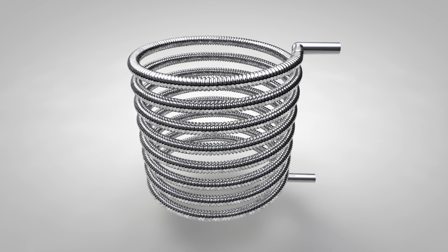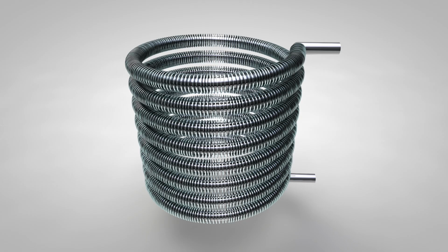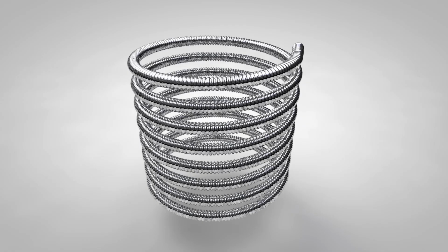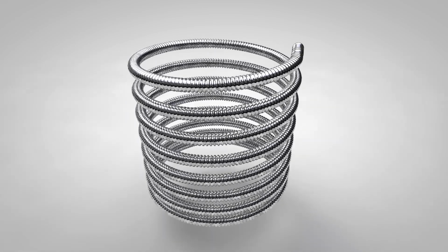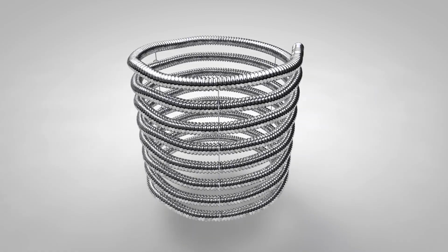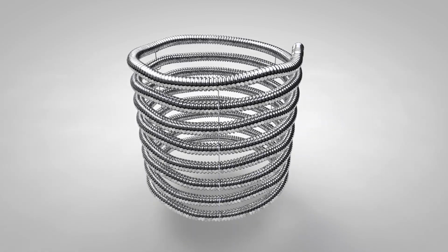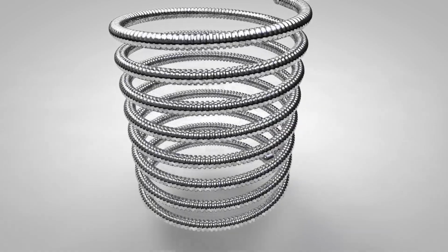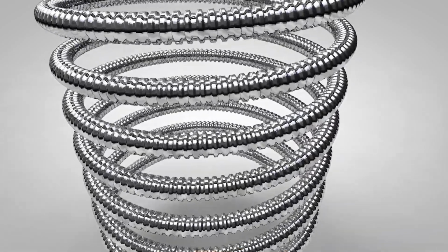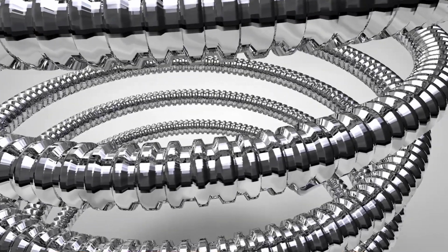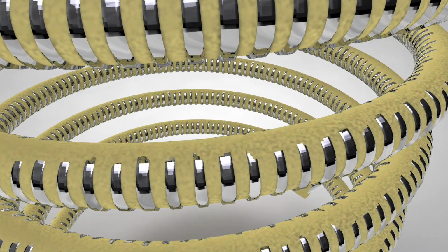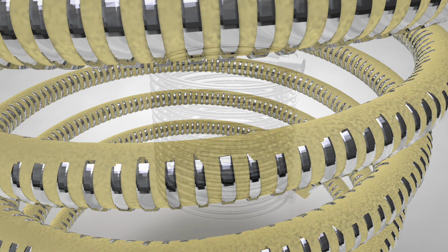3. Some manufacturers use a corrugated pipe or one with fins to increase the surface area. These pipes are very flexible and provide a solution where very large surface areas are needed, such as for a thermal store. However, the pipe is intrinsically flimsy and will shake about inside the cylinder even when supported by clips, making the coil more prone to leaks. The ridges can create turbulence, resulting in noise and reduced flow rates, as well as trapping limescale, leading to reduced heat transfer over time.